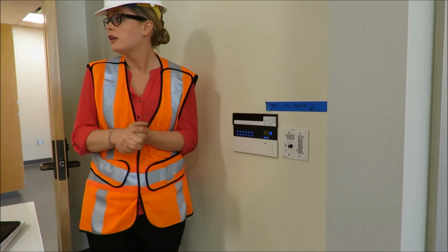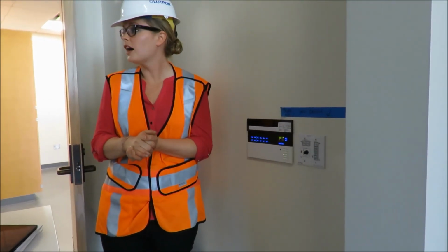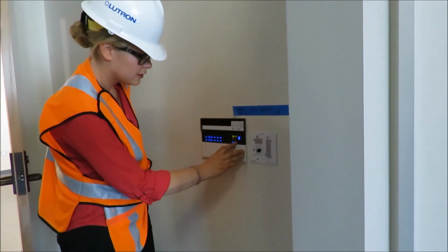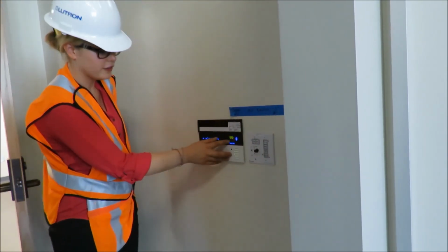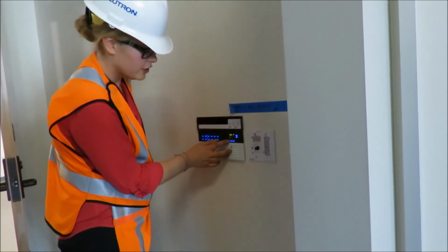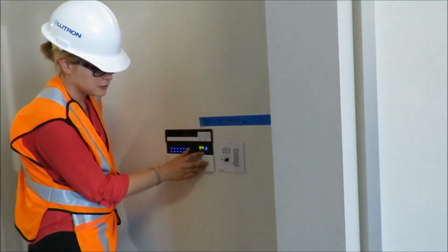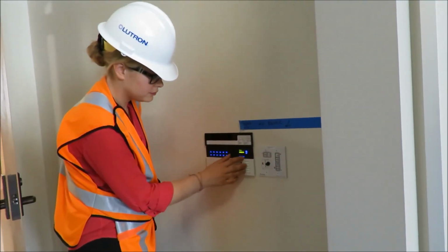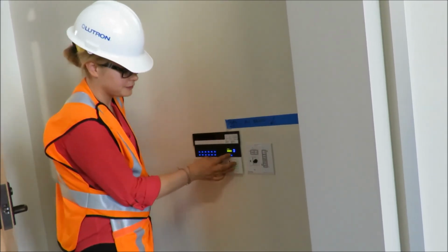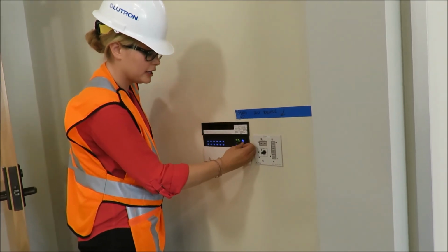How about the sensitivity for that sensor? It's left at default right now. See, there's your daylight sensor, and it's set to zone 3, which is the window 2x2s, but you could change it. If you want it to be more sensitive, you would go into calibrate, and you would have to pick each zone that you have it set to. It even tells you up is more light, down is less light.